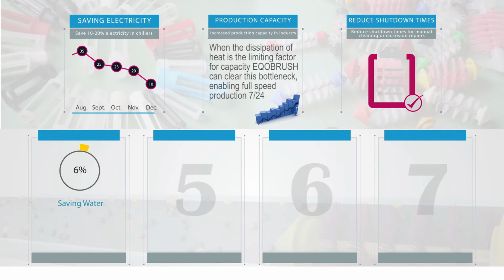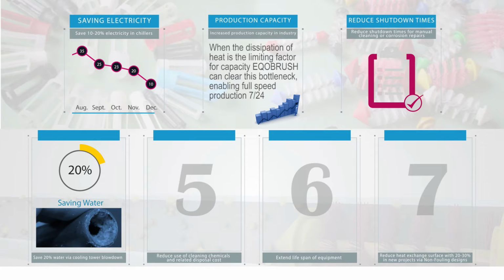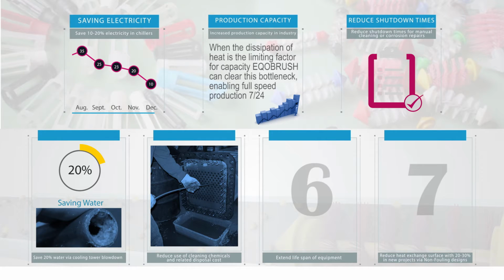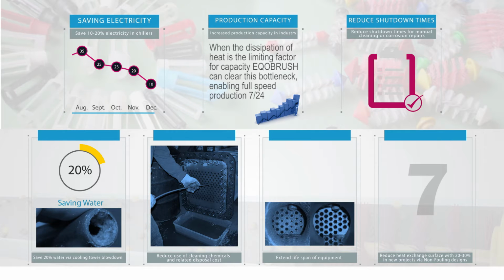Save 20% water via cooling tower blowdown. Higher allowable cycles of concentration of the cooling water saves on makeup water. After all, mineral deposits do not have the chance to settle and crystallize in the tubes. Reduce use of cleaning chemicals and related disposal cost, as releasing cleaning chemicals to sewage systems or surface water is no option. Extend lifespan of equipment. Corroded tubes will start leaking and need to be blocked. With increasing numbers of blocked tubes, the equipment eventually can no longer be used.